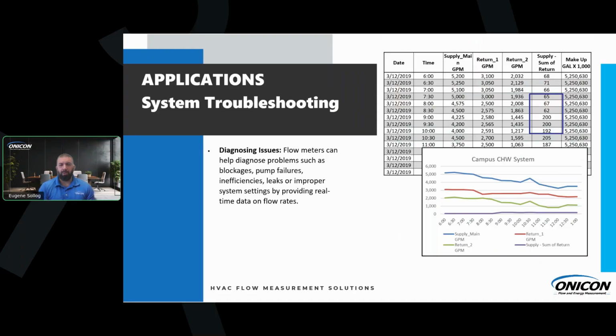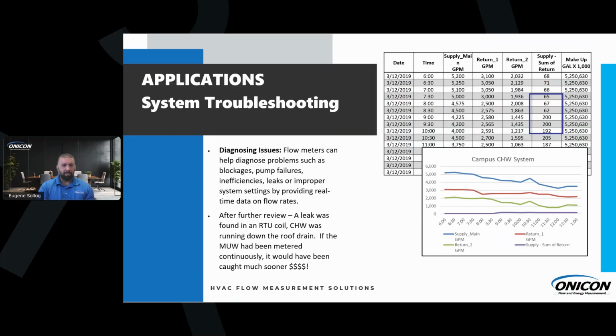Time to look at some troubleshooting that we've seen in the past. This is from 2019, so quite a while ago now. This was actually a leak that happened and was not realized because there was no meter on the makeup water. They were just relying on the city meter to let them know what was going on. After further review, we found the leak in the rooftop unit fan coil, and chilled water was running down the roof into a drain and into the gutter. If they had an individual flow meter on that makeup water, they would have understood that they were using too much water. Instead, they had to learn the hard way, and then realized after the fact that their flow meters were trying to tell them something.